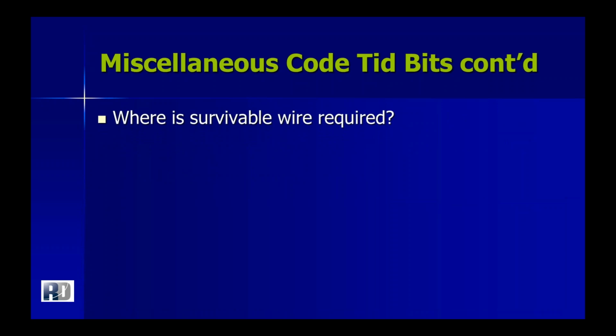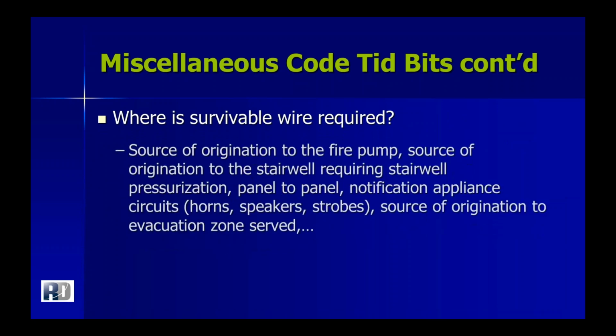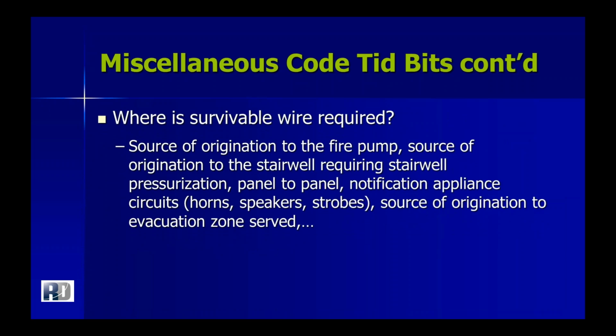Where is survivable wire required? So really, survivable wire is required from the source of origination to a fire pump. It's required from the source of origination to the stairwell that requires stair pressurization. Obviously, once you enter that zone of stair pressurization, you can then run in just regular wire or rings and strings. It's kind of like duct now, where you almost can't penetrate through into a stair zone. You need survivable wire when you're going panel to panel, or any notification appliance circuit, and the source of origination to your evacuation zone it serves. So sometimes you're crossing zones. You need your survivable wire from your origination through the multiple zones, but once you get into your zone, then you can run it in your regular wire or your rings and strings.